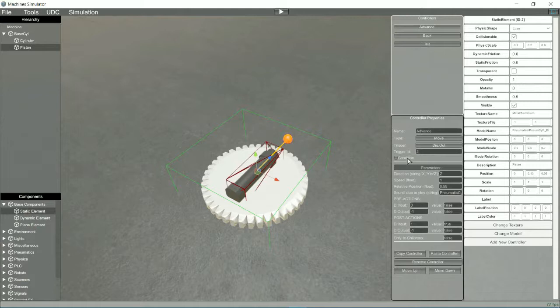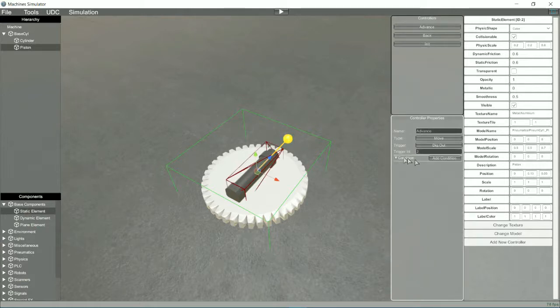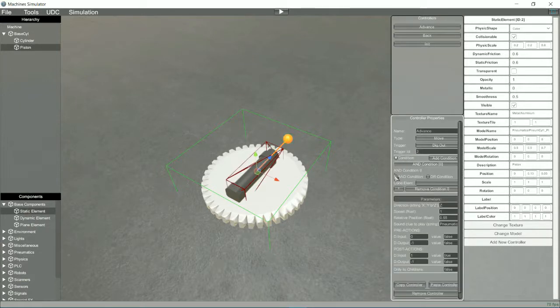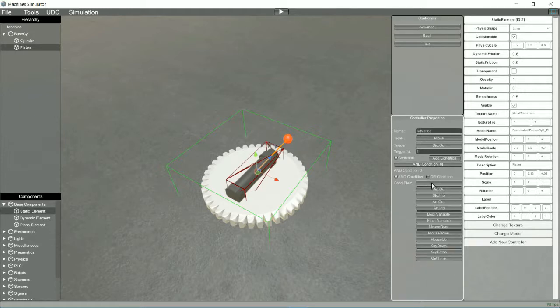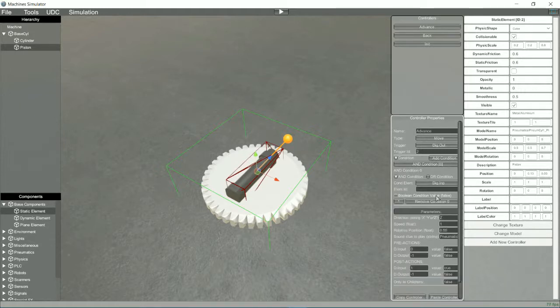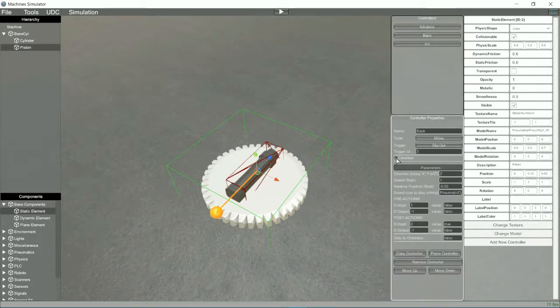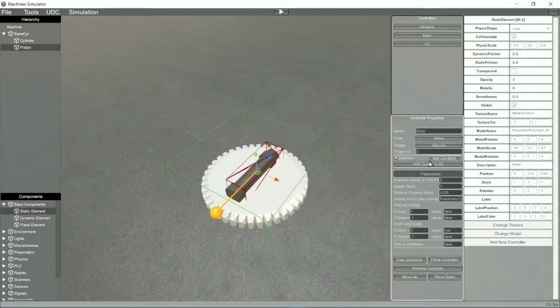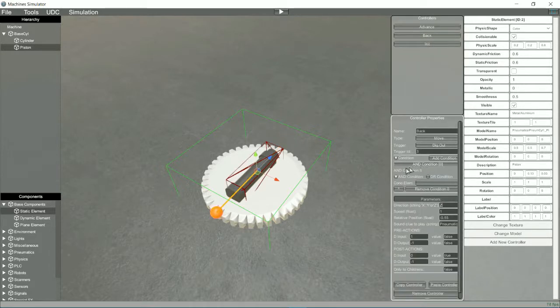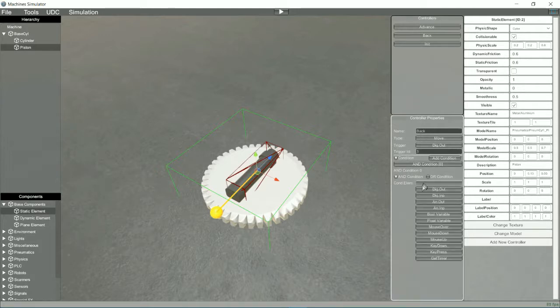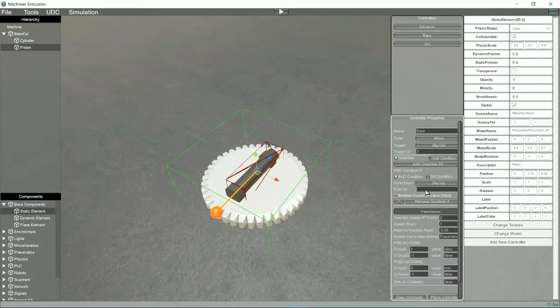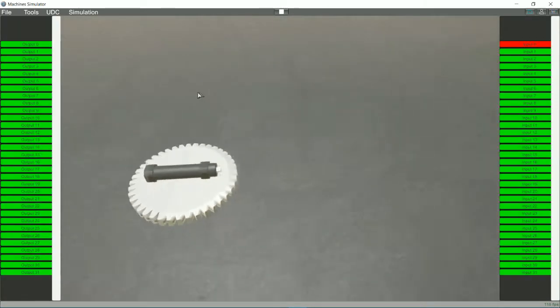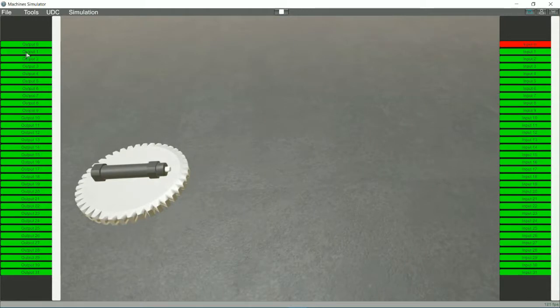Now is the time to use the conditions. With them we can condition the triggers to activate only in certain circumstances. Now we will force that can only move if we are in the right condition. To move the piston forward, we will create the condition of having the digital input number 0 active. To move the piston back, we will create the condition of having the active digital input 1. Now we can check how our system works correctly.